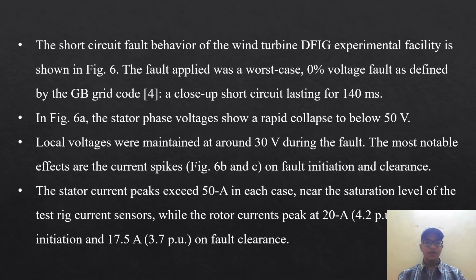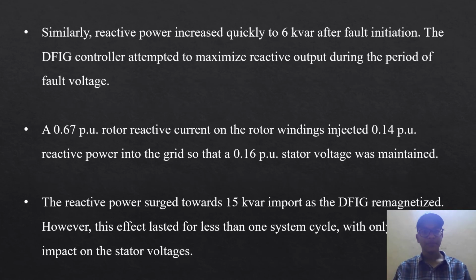Zero voltage faults. The short circuit fault behavior of the wind turbine DFIG experimental facility is shown in the figure. The fault applied is the worst case 0.0% voltage fault, as defined by the GB grid code. In figure 6a, the stator phase voltages show a rapid collapse to below 50 volts. The local voltages are maintained at around 30 volts during the fault. The most notable effects are the current spikes at fault initiation and clearance. Similarly, reactive power increased quickly to 6 kVAR after the fault initiation. The DFIG controller attempted to maximize the reactive output during the period of fault voltage.